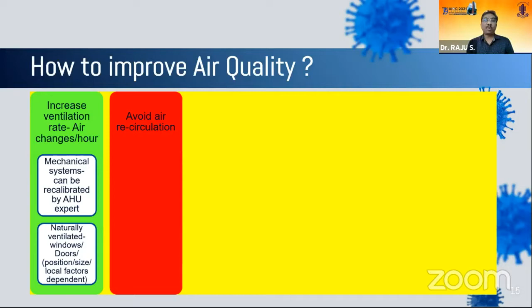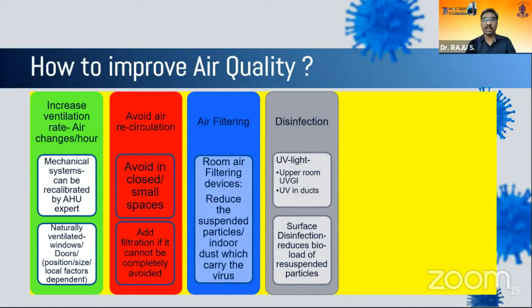The air filtering can be done by using various air filtering devices. The purpose of them is to reduce the suspended particles or the indoor dust, which actually carry the virus all around the room. Next is to consider effective disinfection. That is, you can consider the UV light either into the room or in the ducts, and make sure that you have adequate surface disinfection to reduce the bioburden, because this dust which has settled again gets resuspended, and this again can cause infection.